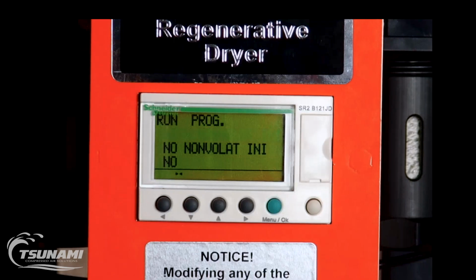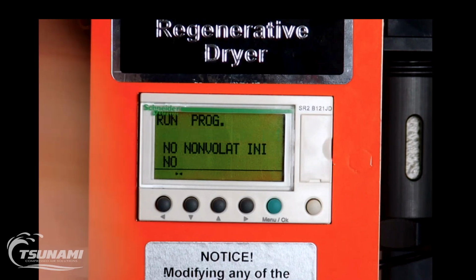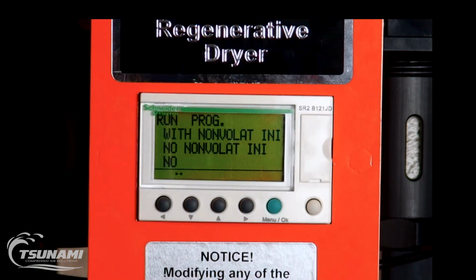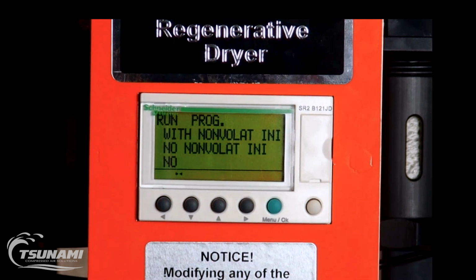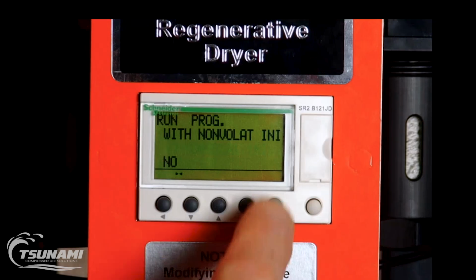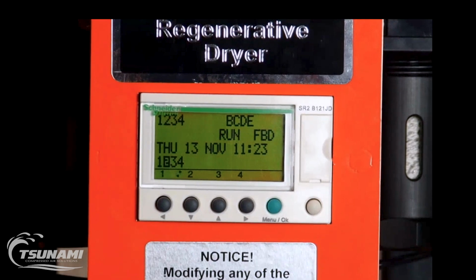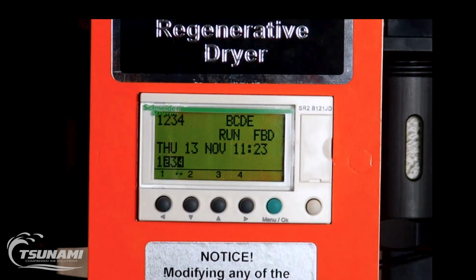So the program that's in this PLC has a timer to tell you when to replace the coalescing element. And so when it comes to that, we don't always want to reset all those values. Maybe you changed it 5 months ago and now it won't flash up its little warning on the display to tell you to change it. So more often than not, we are going to tell you to hit the down arrow until no non-volatility is flashing and hit OK. Now the program is started. We did not reset any of what are called latch values inside, or the timers.